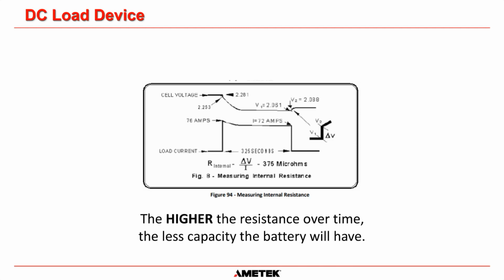So what the cell corder does is it actually has a bank of resistors inside the cell corder and a contactor or a relay. And when you press the button, it actually puts a load on that one cell that you are testing, or that one block that you are testing. And that load is usually between 50 and 70 amps. And you can see on the screen here, this is from the Alber Cellcorder manual, this is what it does.